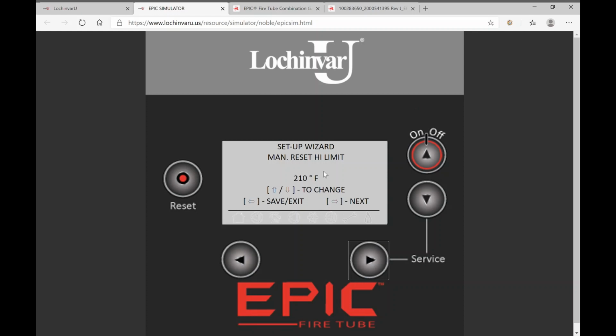The next one is our manual reset high limit. Once the boiler hits 210 degrees for whatever reason, the boiler will go into a manual reset, and we'll have to actually go there and physically reset the boiler, which you can see is on the left hand side here. The next setting is our domestic hot water set point. On the combi boiler, we're going to adjust this for whatever we want the plate heat exchanger inside the unit to produce. Or if we're using an indirect water heater, we can adjust this too. It's what we want our set point in that tank, or coming out of that plate heat exchanger, to be. In this case, it's 120. On the combi, I believe we can go up to about 150.